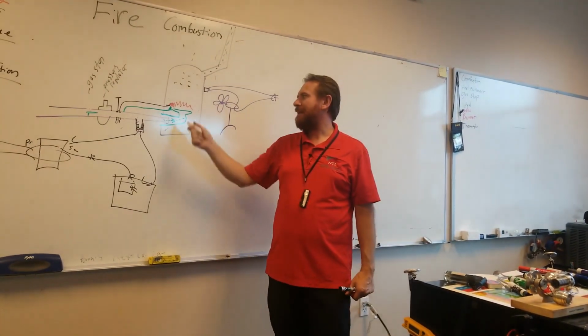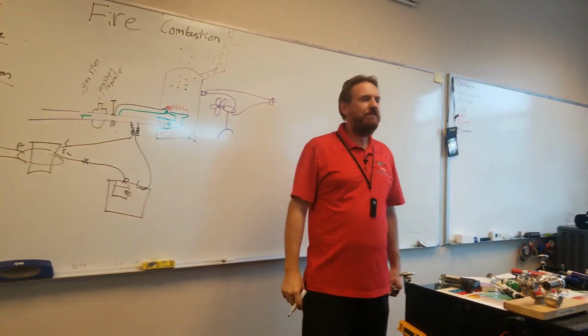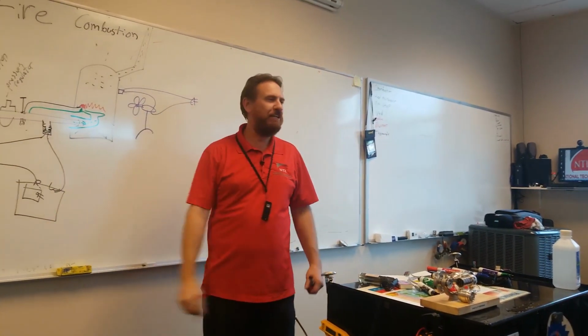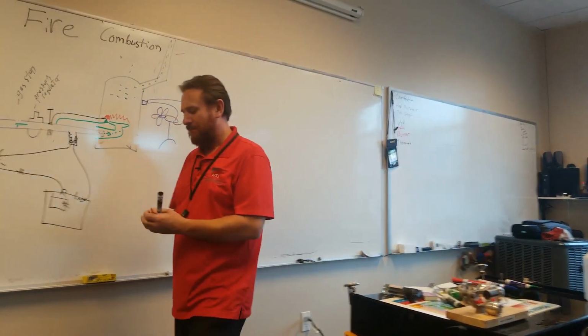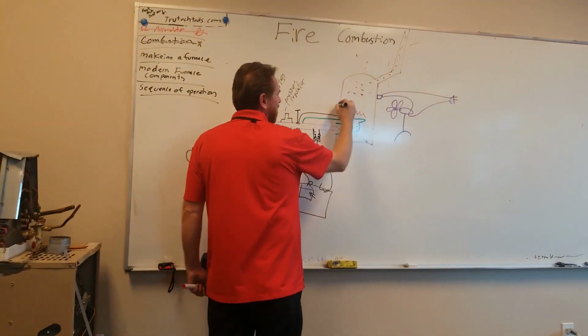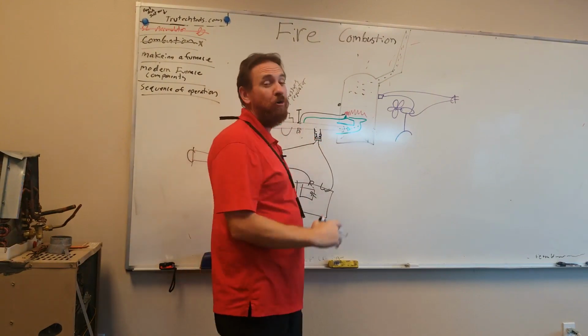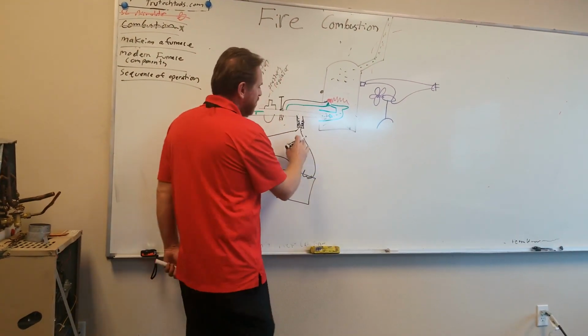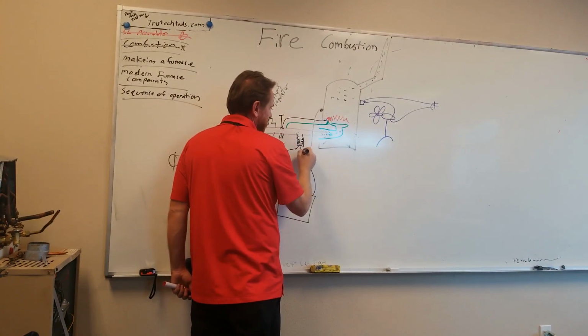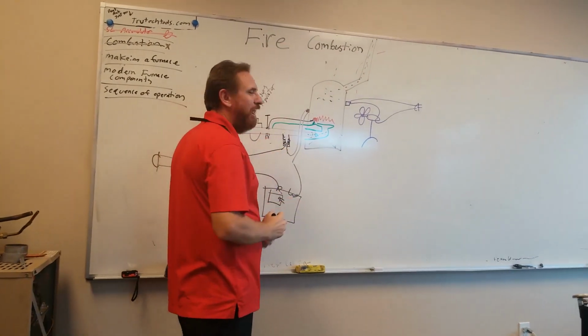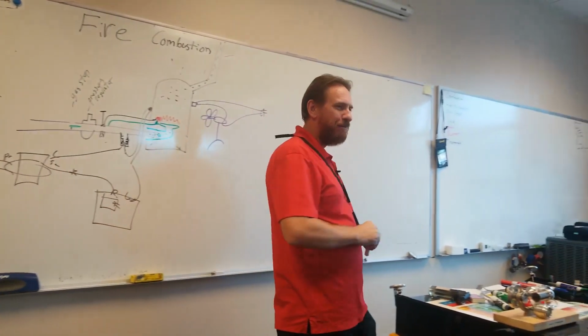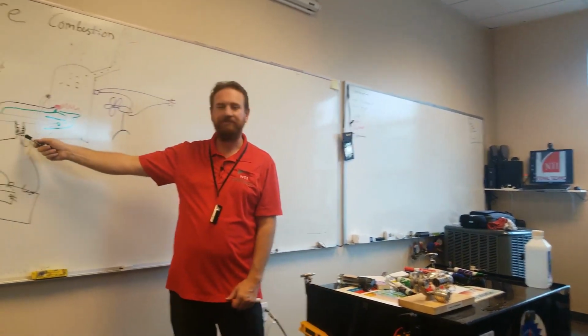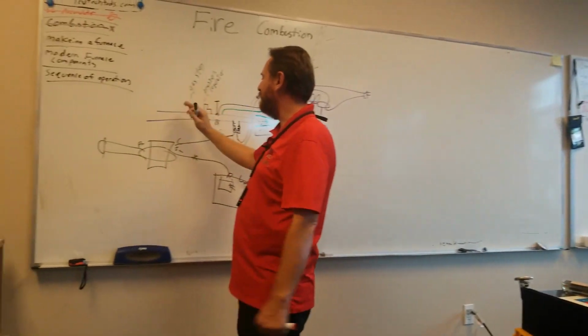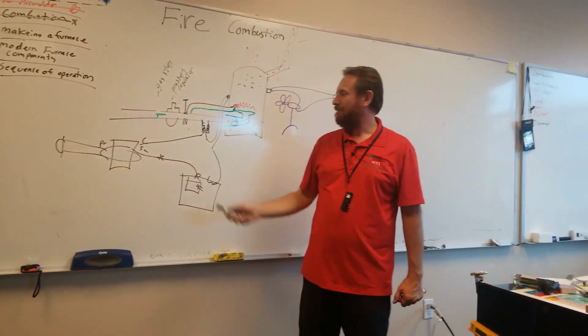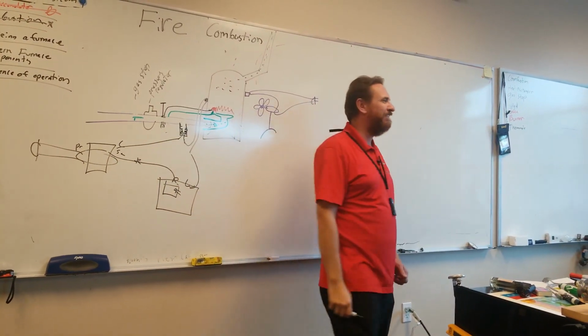But what if something happened and this got too hot? What if I had a safety on here to prevent this from getting too hot? Maybe I would put a sensor right here that's normally closed and it opens on temperature rise. And this W wire, I break it. So if it gets too hot, it would shut off the combination gas valve. I'm sorry, the solenoid valve. Isn't that cool? And I still have my main gas stop over here, so if I need to work on anything, I can shut it off manually. But I got my automated controls here that turn on and off as I need.